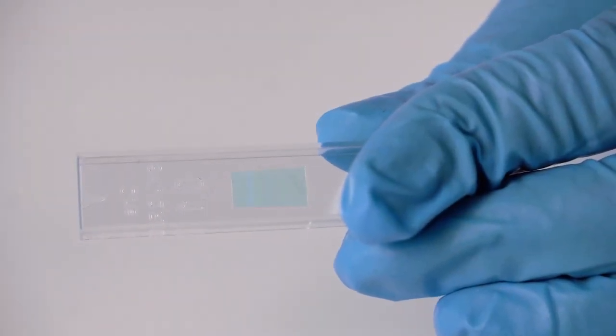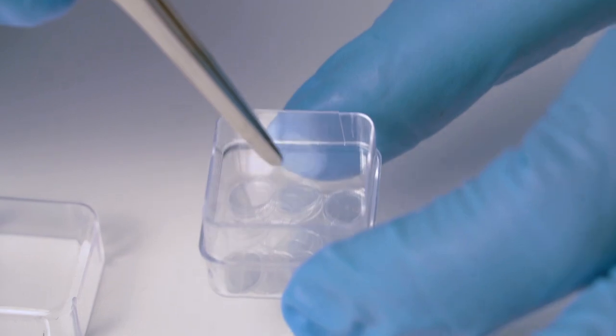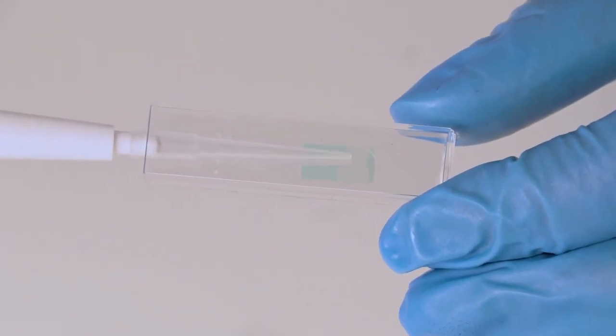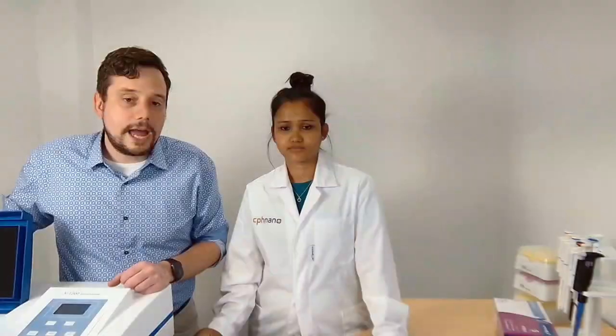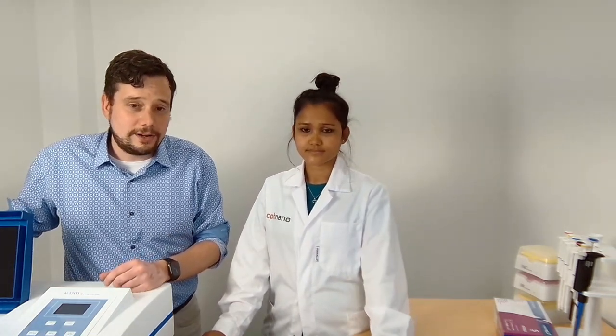For a full 3 mL measurement, simply fill the cuvette with your liquid sample. For a 0.5 µL or 1 µL measurement, you hold the cuvette horizontally, apply your sample using a pipette on top of the photonic crystal, then place a cover slip — included in the NanoCuvette 1 packaging — on top of the drop. Use the tip of the pipette to carefully position the cover slip and form a film between the photonic crystal and the cover slip. Then insert the NanoCuvette 1 with the sample into your instrument. It measures in exactly the same way as filling the entire cuvette. It's quite easy to do in practice.